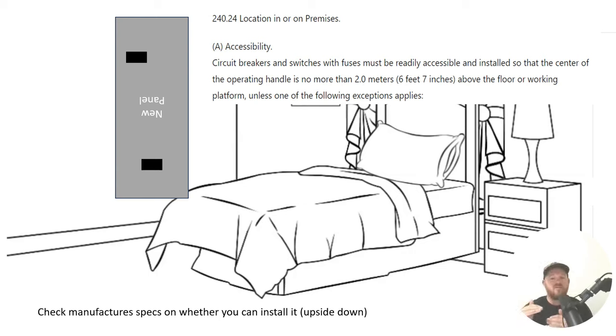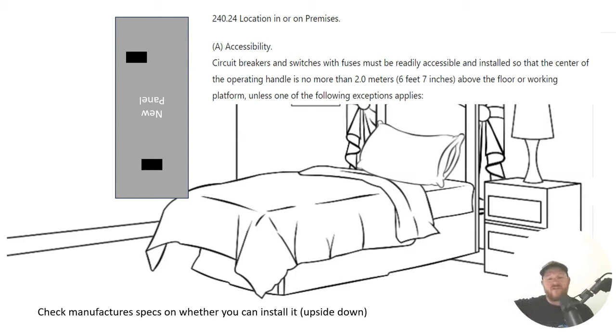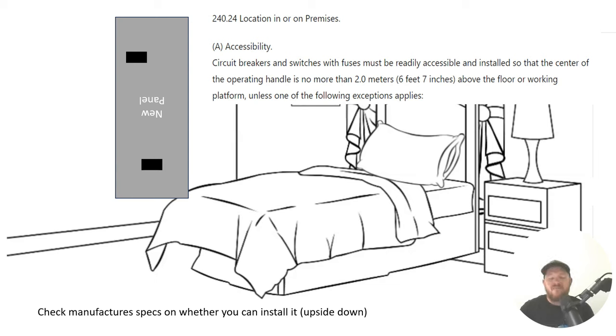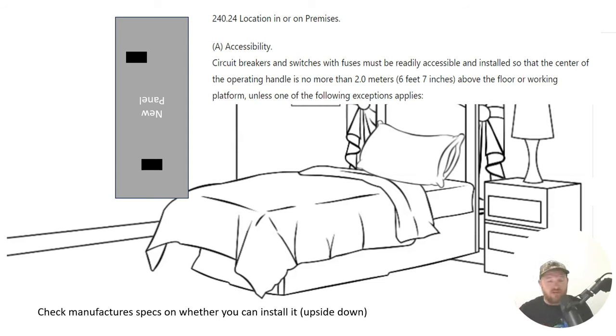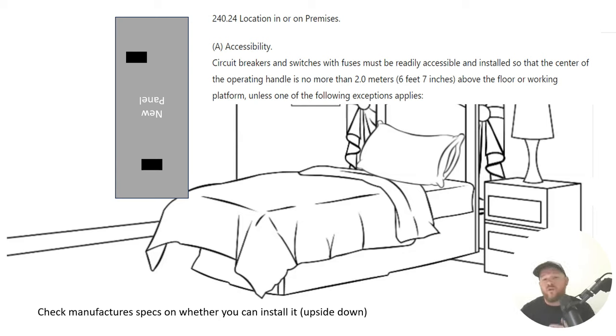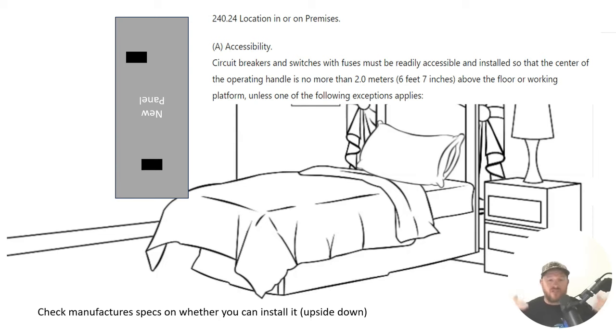And there are a few exceptions down below. And usually it has to do with supplementary overcurrent protection. So let's imagine you had a piece of equipment and it also had a localized disconnect right there next to the equipment. As long as the breaker that's feeding that branch circuit is lower than 6 foot 7 and accessible, then it's okay because you can turn it off at a readily accessible location. Then up there, if you want to have another breaker or fuse, that's likely going to be okay. That's one of the scenarios where you are allowed to do it. But just as a blanket statement, under most circumstances, all of your circuit breakers are going to need to be below 6 foot 7. So just keep that in mind.